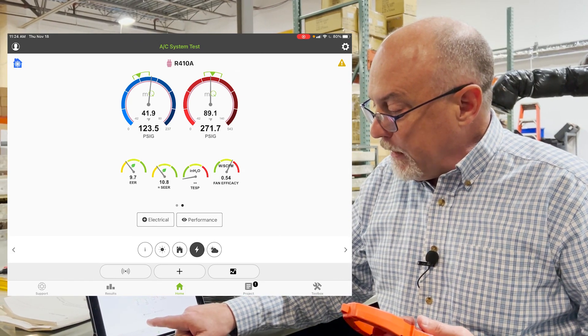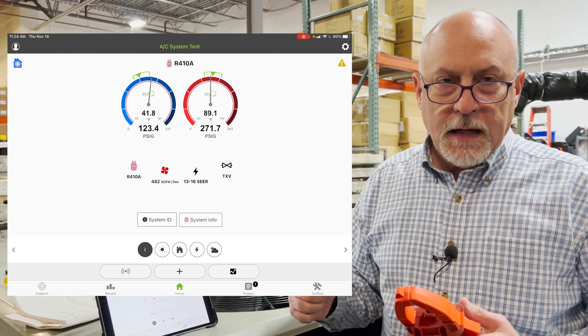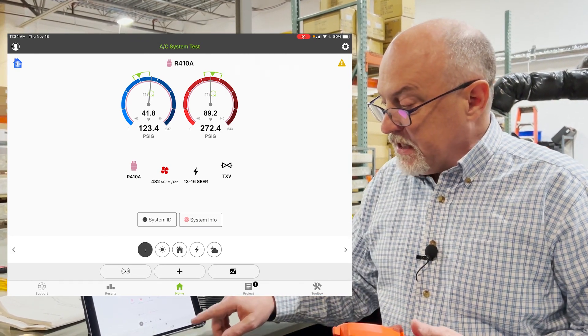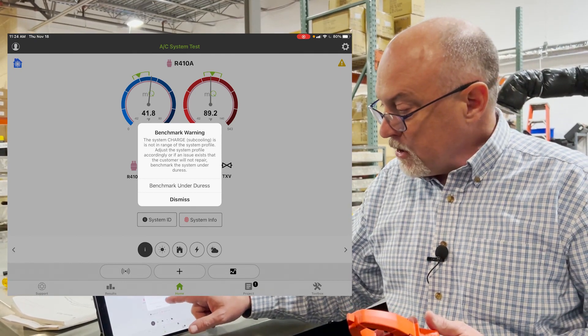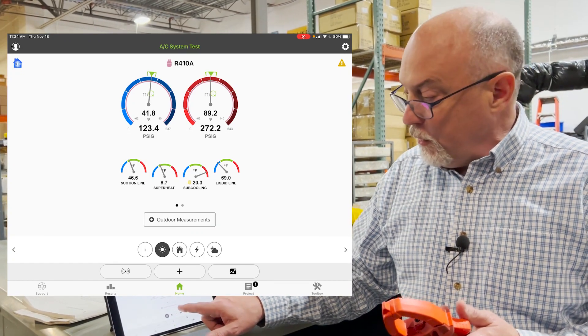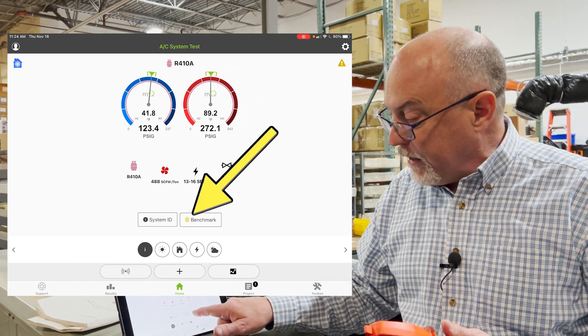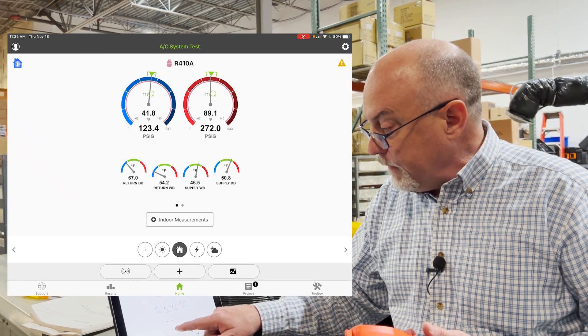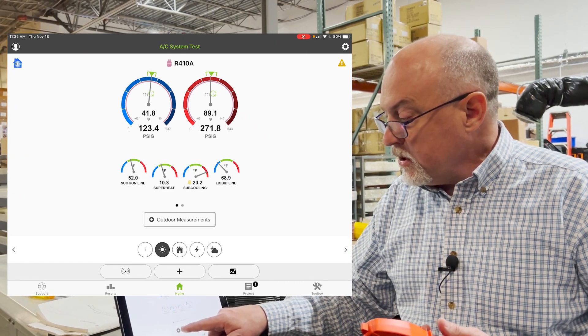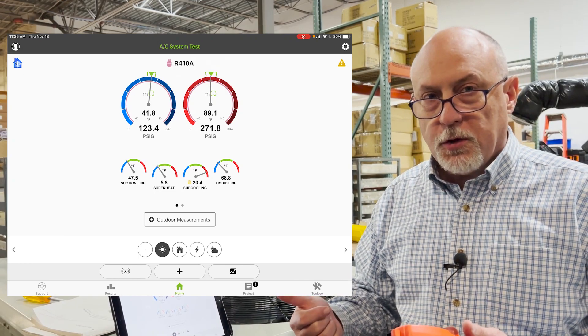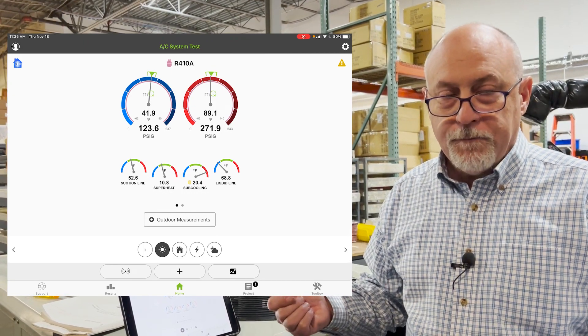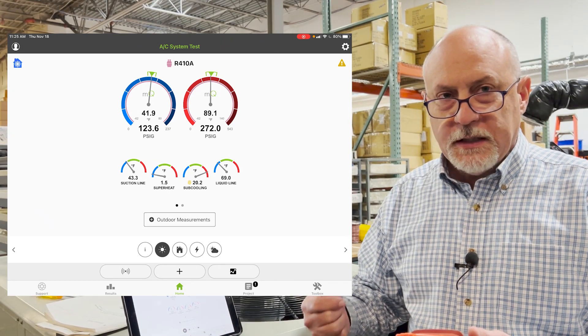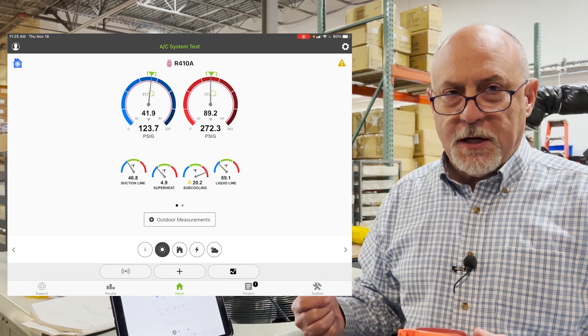Now, also, I just wanted to point out here on the benchmarking side. So I'm going to go back to the info screen. You can see that system info right now has got a red thumbprint. And again, we talked about benchmarking is capturing the personality. So if I wanted to say, hey, Mrs. Jones isn't going to do anything with the system, I'd hit the plus key here, and I'll set a benchmark. It's going to bring up a benchmark under duress. So I'm going to click that for just a minute. We show it's been benchmarked and it's under duress. If we go back here, you're going to see that there's a yellow thumbprint on here now, and there's a yellow thumbprint here on the benchmark, a yellow thumbprint right here in the subcooling, showing us that the subcooling is too high. And then also, if we scroll through here a little bit, we'll see if there's any other yellow thumbprints, which there's not because everything else would be acceptable. So it's just showing us when we left that unit, it was benchmarked, but the yellow benchmark means it was benchmarked under duress. If we got the subcooling right and we re-benchmarked it, it would benchmark green, telling us that everything is good. So red is not benchmarked, yellow is benchmarked under duress, green is benchmarked, and everything was in the correct ranges on there. So we added this feature in to make it a little bit easier to understand what the benchmark's doing.